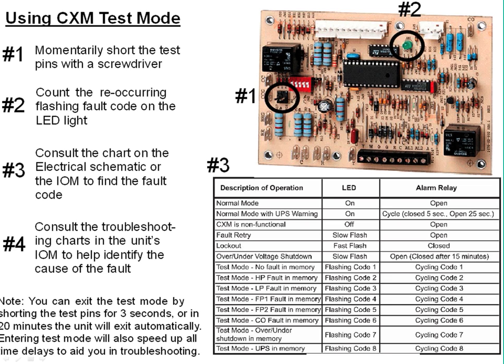So here's an example of the CXM board in the typical residential product line. You're going to see number 1 circled there. That is your test pins. Item number 2 circled on your screen there. That is the LED status light. That lets you know whether the system has a call or it's operating, or if it has a fault in memory. Please, guys, never, ever, ever send a homeowner with a butter knife or a screwdriver or anything else anywhere near this circuit board, okay? Only for your eyes and your tools only.